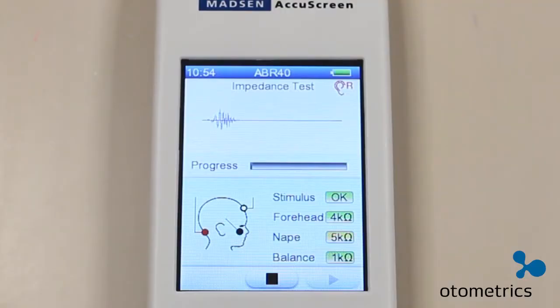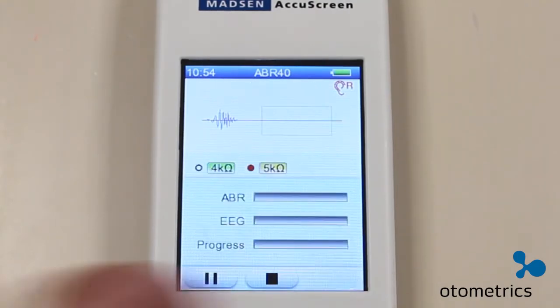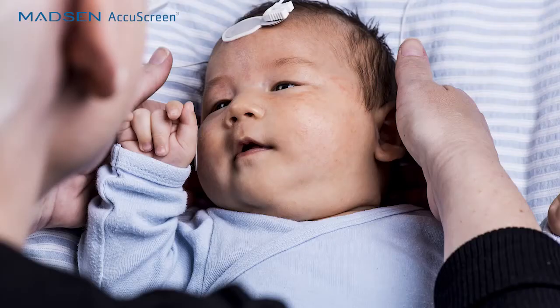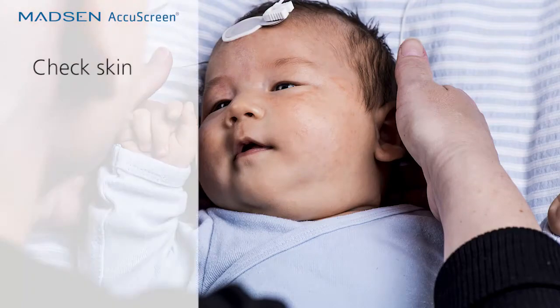Before the ABR test can proceed, the Accuscreen measures these important variables. Depending on your setup, the ABR test can start automatically when the values are within the limits, or you may have to press the start button manually to begin the test. If the system reports too high impedance values, measures must be taken to try to reduce the impedance before any test can be performed. Check if the baby's skin is very dry.